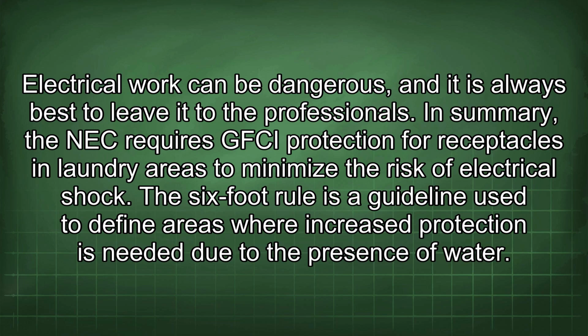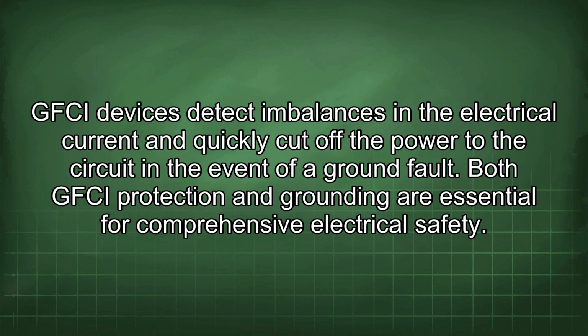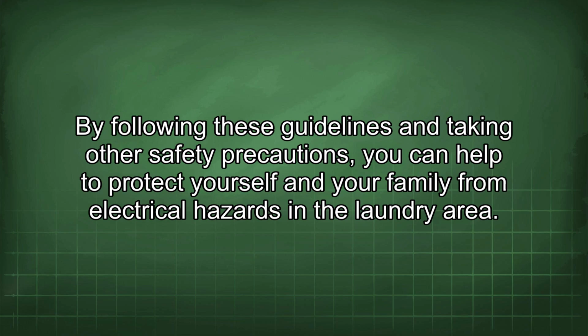In summary, the NEC requires GFCI protection for receptacles in laundry areas to minimize the risk of electrical shock. The 6-foot rule is a guideline used to define areas where increased protection is needed due to the presence of water. GFCI devices detect imbalances in the electrical current and quickly cut off the power to the circuit in the event of a ground fault. Both GFCI protection and grounding are essential for comprehensive electrical safety. By following these guidelines and taking other safety precautions, you can help to protect yourself and your family from electrical hazards in the laundry area.